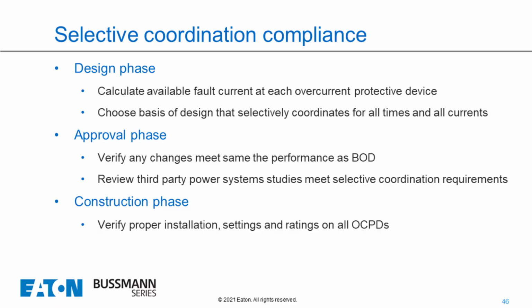Remember, all times, all currents. All times do not say 0.01 seconds or 0.1 seconds. It's 0 all the way up. Because if we're at 0.1 seconds, that's still over a half a cycle. And the National Electrical Code says all times, all currents.